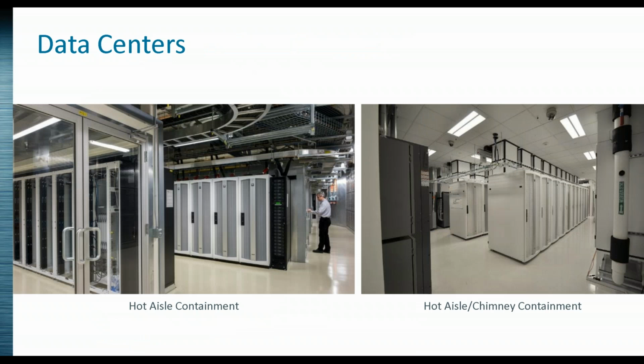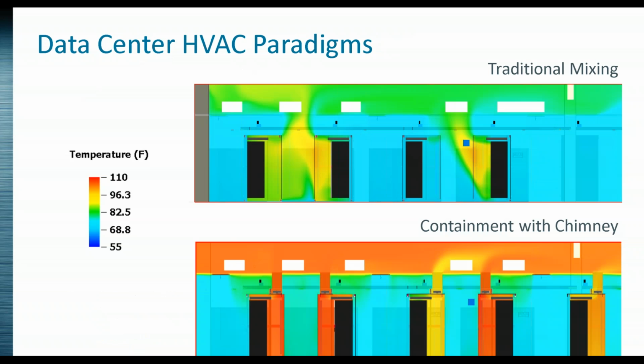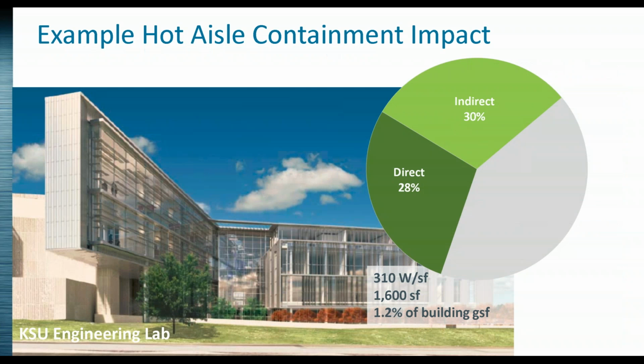Looking at hot aisle containment and the hot aisle/chimney containment approach becomes a significant opportunity. In the past we'd traditionally mix all the air in the space, which meant putting in a lot more air because the cold air was getting warmed up by air blowing around, making it less effective at cooling the equipment. Now, if we deliver cold air to the equipment and pull the hot air off the back or top, we can really reduce the amount of air needed.